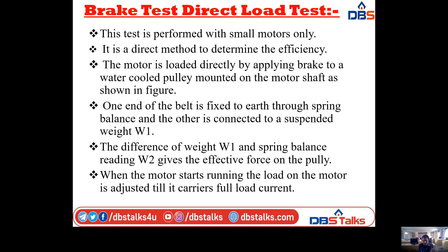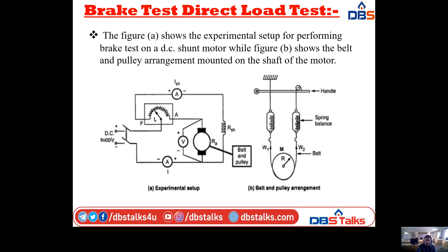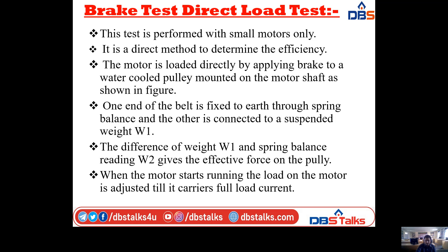One end of the belt is fixed to earth through a spring balance; the other is connected to a suspended weight W1. W2 is fixed and W1 is varied. The difference between weight W1 and spring balance reading W2 gives the effective force on the pulley. The load is adjusted until the motor carries full load current.